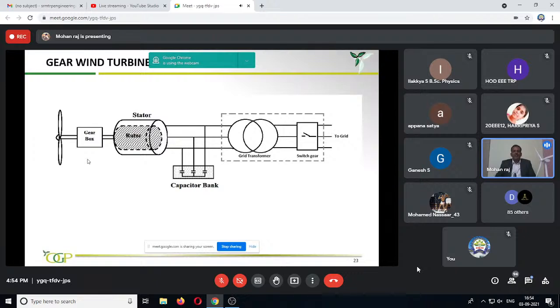So the induction generator will automatically synchronize to the grid when it has a negative slip, when it goes above the synchronous speed. This capacitor bank is used for managing the reactive power which is generated by the wind turbines. You see, it is a grid. Further, it is connected to the grid transformer, and further there are switchgear like circuit breakers, SF6 breakers, and vacuum circuit breakers available for isolating in case of any faults. In case of any faults in the grid, it will get isolated from the grid.